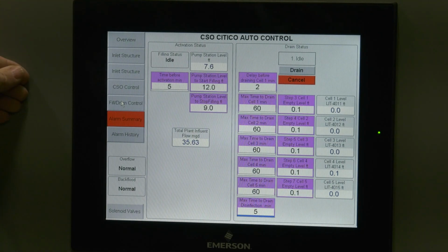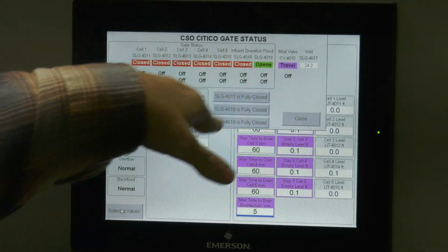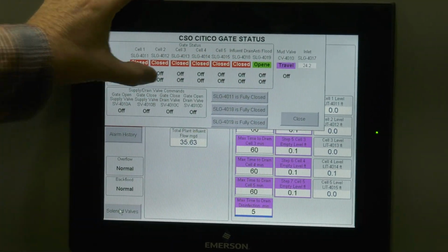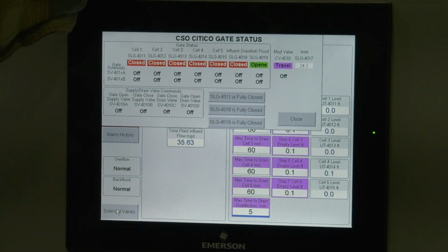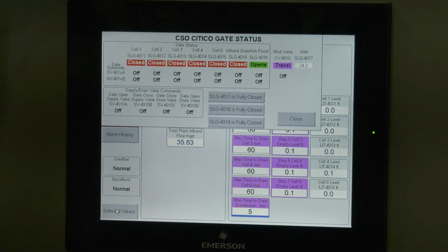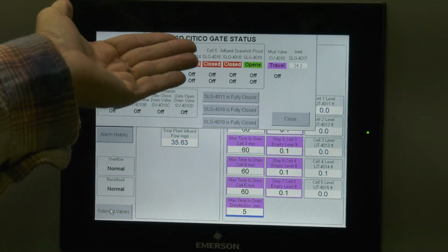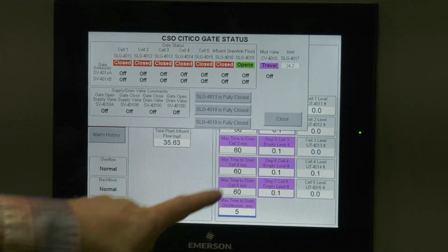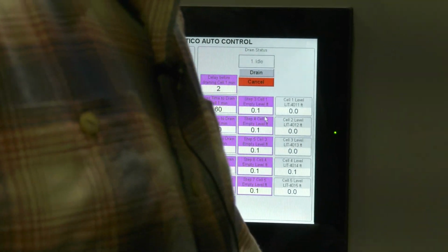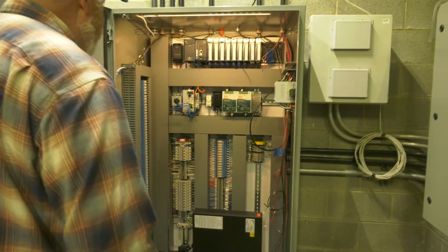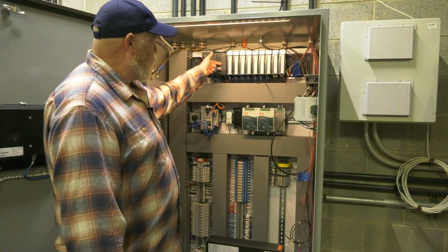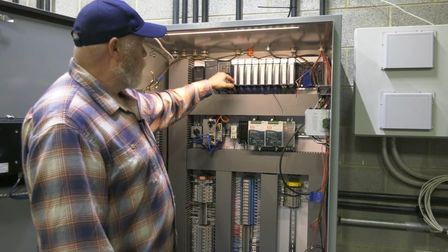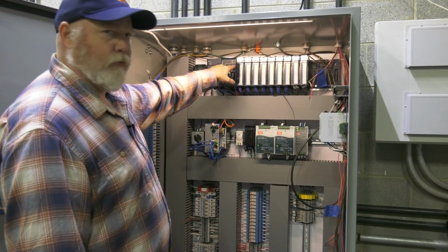Okay, and let's see, we've got the solenoid screen here. It tells you which solenoid's open so you can help troubleshoot or see what step you're in. Or if a gate's not opening, you can come here and say, well, the solenoid's on, the gate's not opening, we have a problem. All right, so inside of here, again, we've got our PLC processor, the switch here, make sure it's on run with IO.